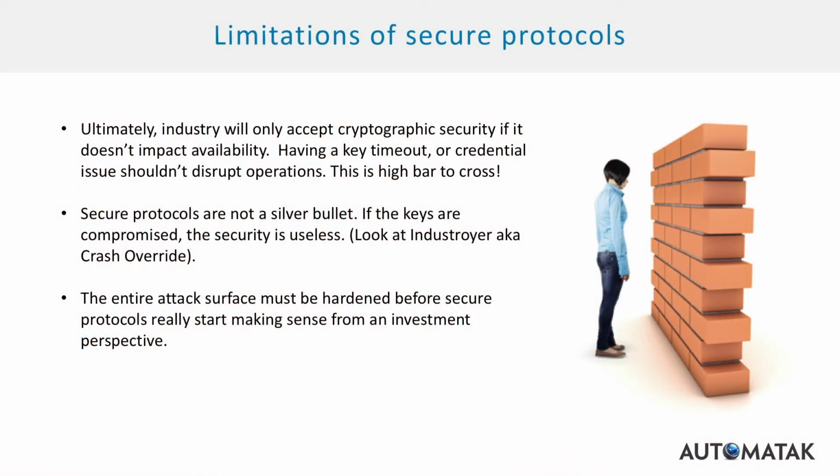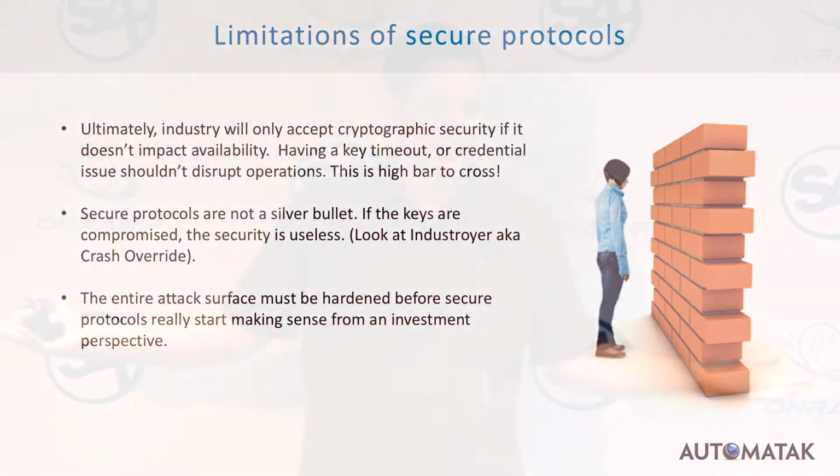Secure protocols are also just not a silver bullet. You'll probably hear more from Rob or others later in the day about Industroyer, or CrashOverride, the attack against the Ukraine a couple of years ago. In that example, they compromised the communication server, which would have the cryptographic keys. So if you let your keys get stolen, secure protocols don't help you. In a lot of the attacks, people have gone after the communication server. If you don't harden that attack surface, these secure protocols just aren't going to help you.